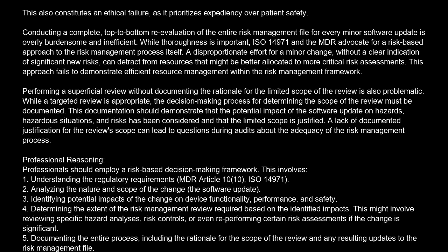Performing a superficial review without documenting the rationale for the limited scope of the review is also problematic. While a targeted review is appropriate, the decision-making process for determining the scope of the review must be documented. This documentation should demonstrate that the potential impact of the software update on hazardous situations and risks has been considered, and that the limited scope is justified. A lack of documented justification for the review scope can lead to questions during audits about the adequacy of the risk management process.